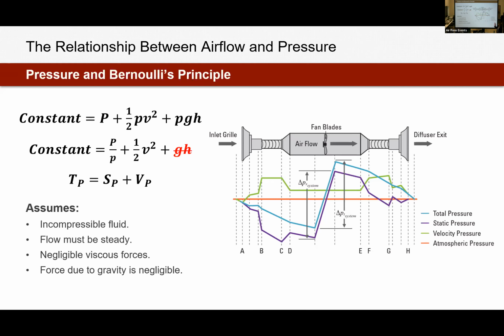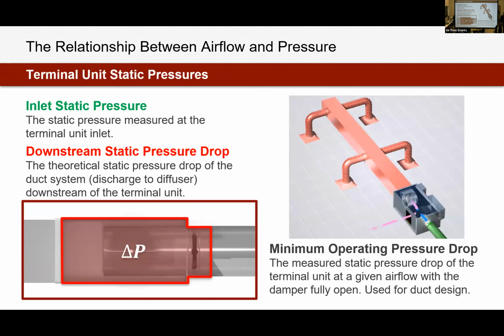Through some deductions with Bernoulli's principle, we're going to end up with this equation right here. Total pressure equals static plus velocity pressure. Static pressure and velocity pressure are the two main components to our system. And how do those come into effect? So the first is going to be your inlet static pressure.